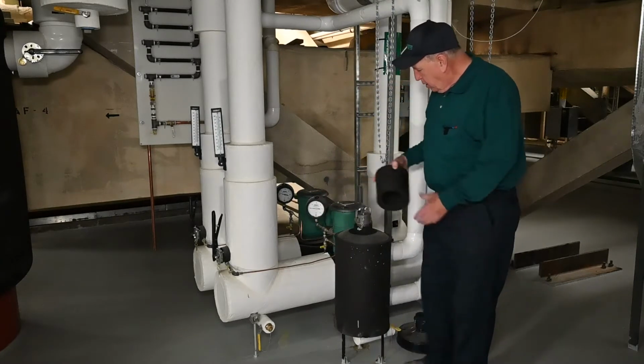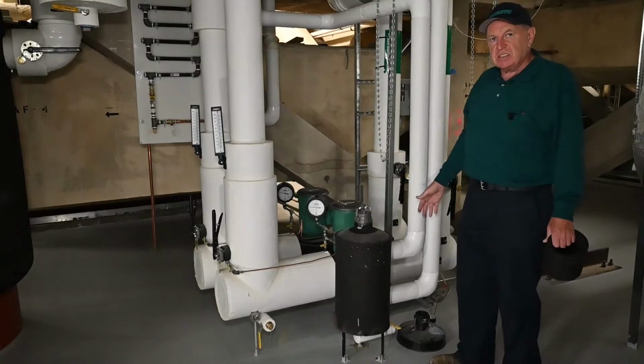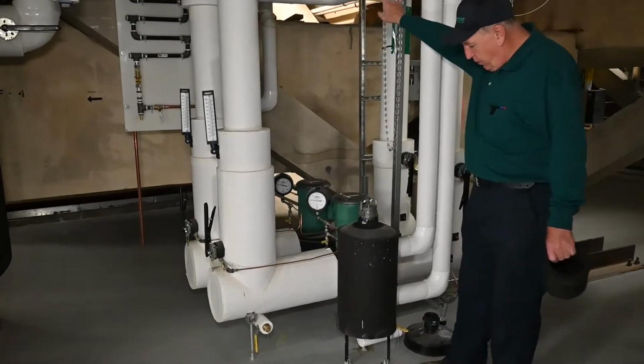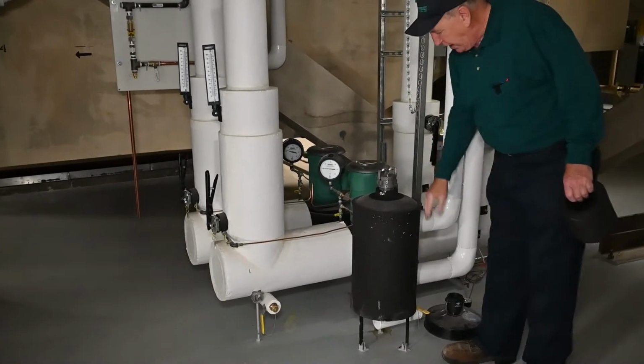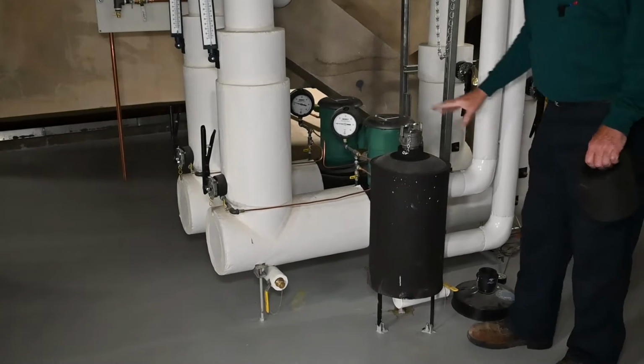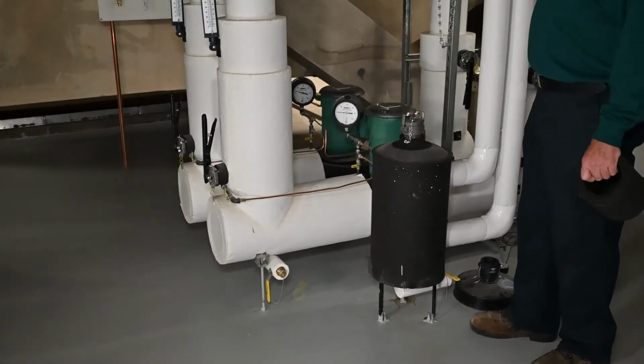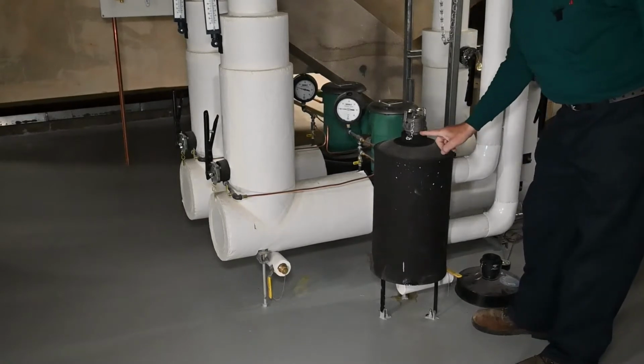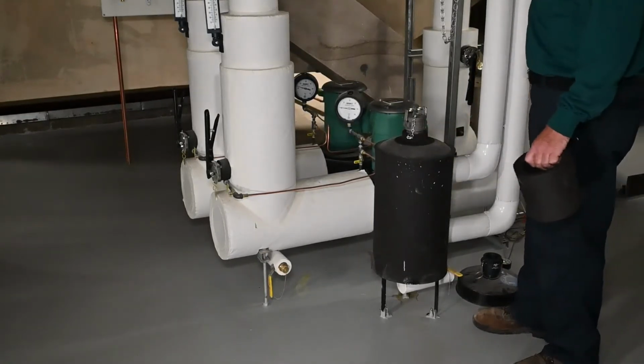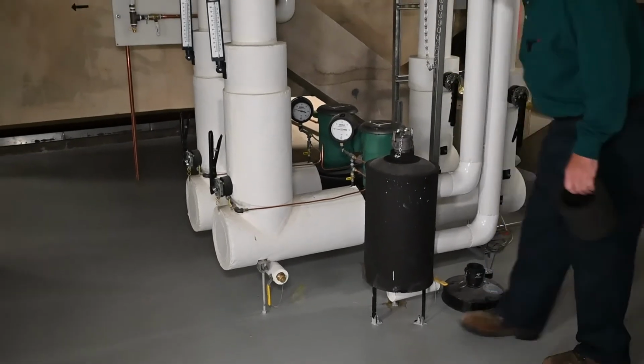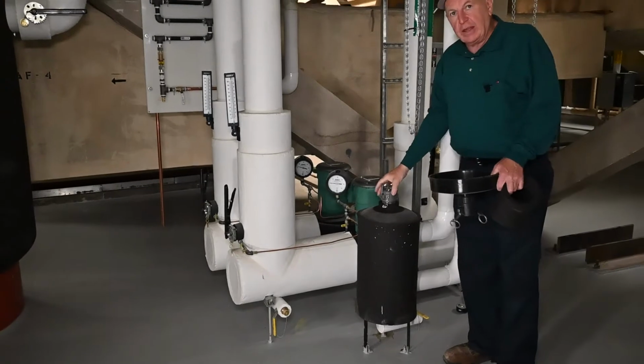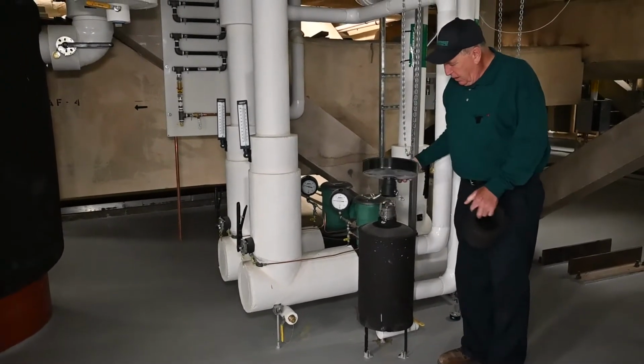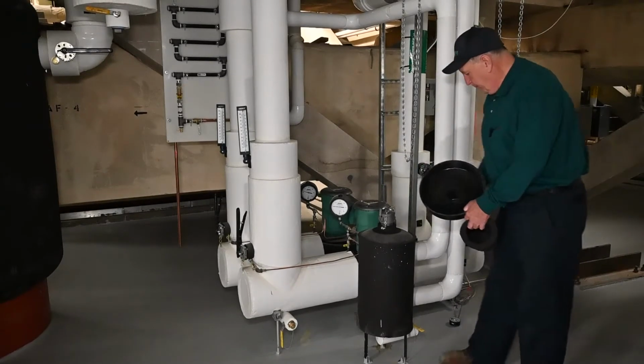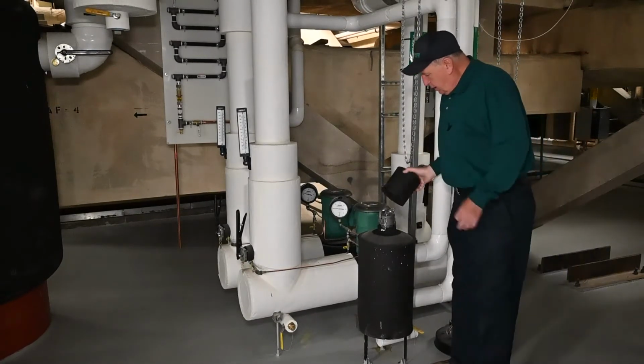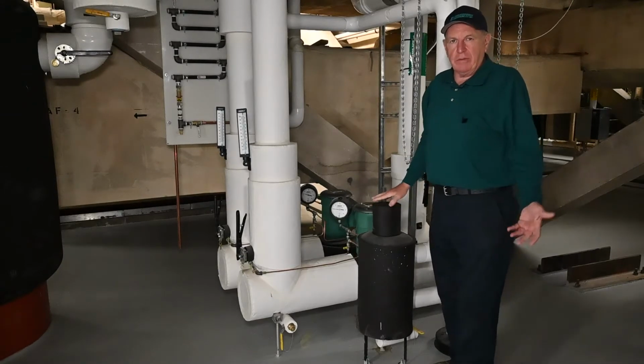But this is a shot feeder, so if you had to add inhibitor to your system, first you drain it, you open this, you add your chemicals, close it up, then open the in and outlet valves, and the discharge of the pump will push the system water through here and add the chemical to it. There is a fill funnel here, but make sure the valves are off before you open the top. Pour your chemicals in, and you probably have a water treatment company with the library. I'm not sure.